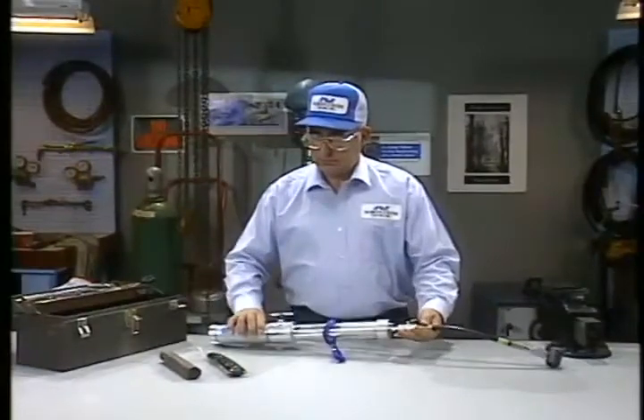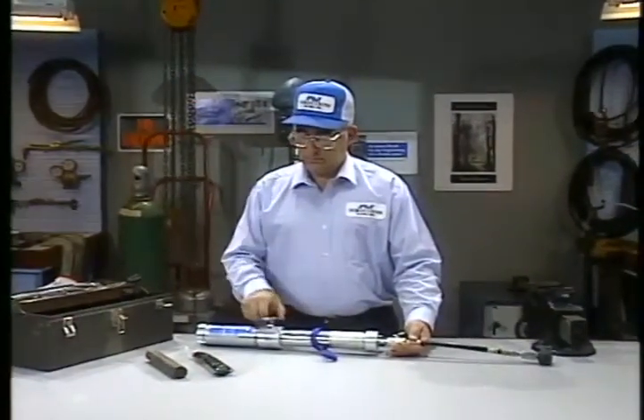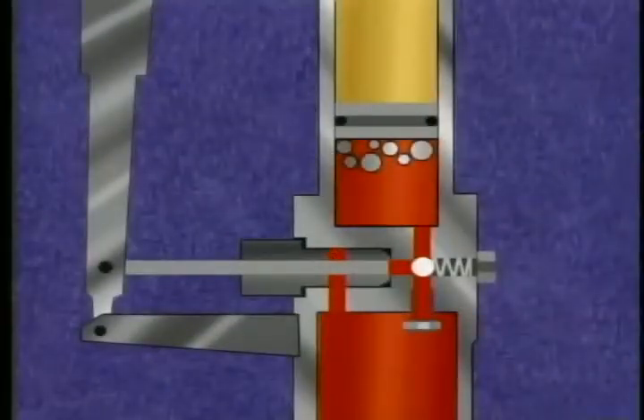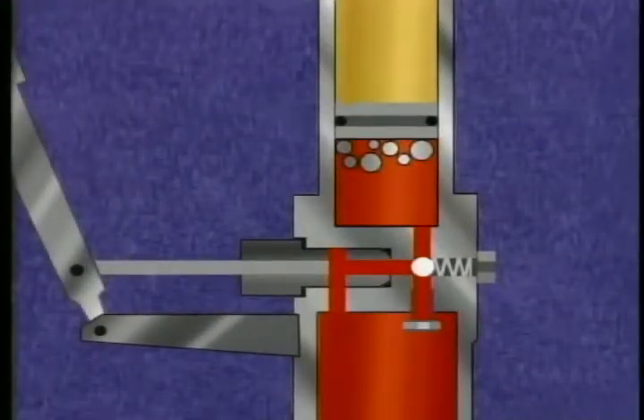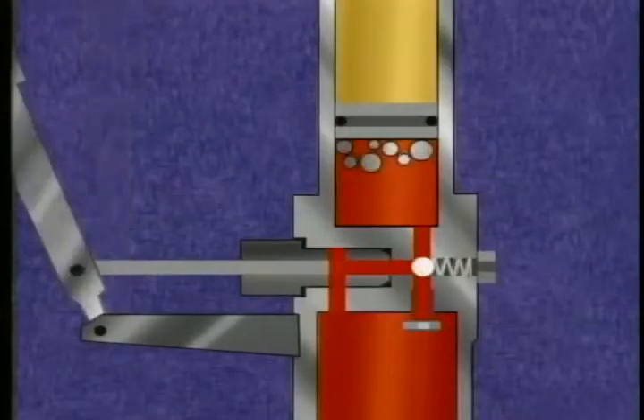The most common maintenance problem is the presence of air in the handgun hydraulic system. The handgun's bypass valve seals with a small O-ring. If this seal is damaged, air may enter the hydraulic system. If air is present in the hydraulic system, the 400D handgun may not operate when the hose end of the gun is pointed upwards. Instead of moving the floating piston, the hydraulic system just compresses the air bubbles.